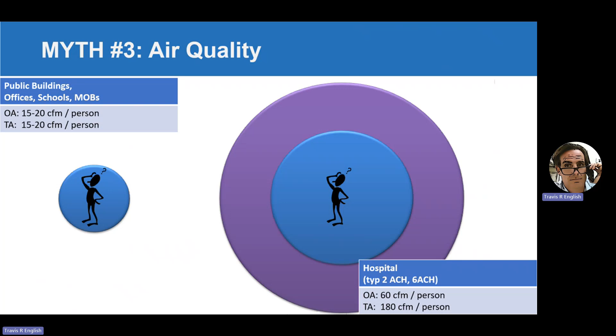And both of these are false. Neither one of them is true. Healthcare ventilation rates do not come from any analysis of contaminant generation. They don't come from any analysis of air quality targets. There's never been an adjustment of air quality targets for susceptible individuals. In fact, there's never been any numeric or quantitative analysis at all of the ventilation rates that we have in the standard. And furthermore, we've done the research.